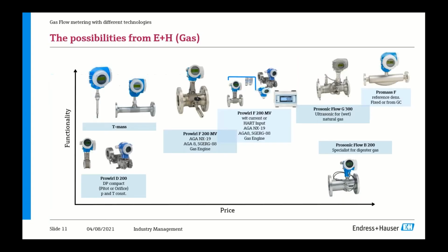And with the next slide, you see a comparison of the different technologies that we will talk about today. We, of course, as Endress+Hauser, can offer you on the bottom left DP flow technologies that are compensated by pressure and temperature, but we can also offer you volumetric technologies like Vortex and the Ultrasonic. So both are available with integrated pressure and temperature compensation, and the real gas equations like AGA NX19, AGA8, and so forth. But we also have, that's perfect choice for utility applications, the thermal mass flow meter that is also available with insertion technology, so available for large line sizes. And top of the notch, from my perspective, is actually the Coriolis technology, where you have direct mass measurement with an accuracy of 0.25%, which is unreachable for all the other guys. That being said, I'll go to the first technology that we want to check out today, and that's the vortex.